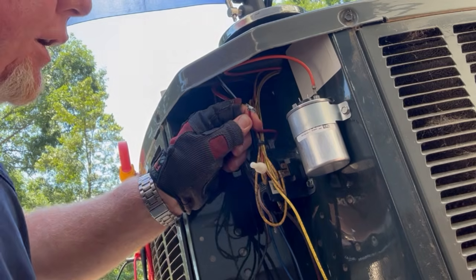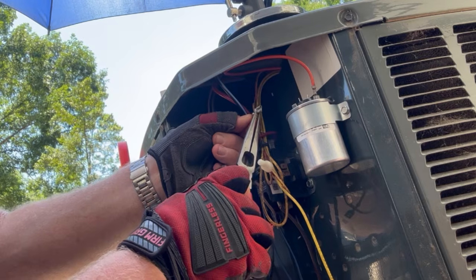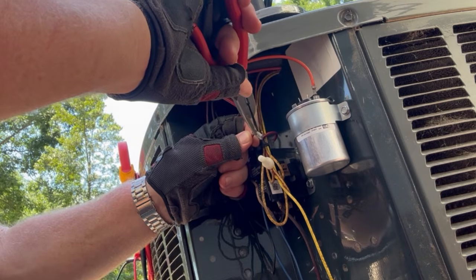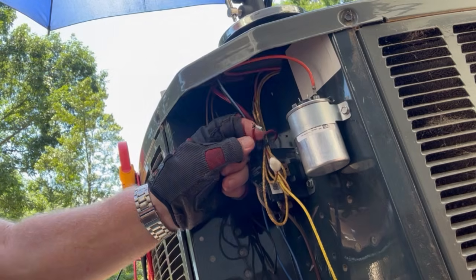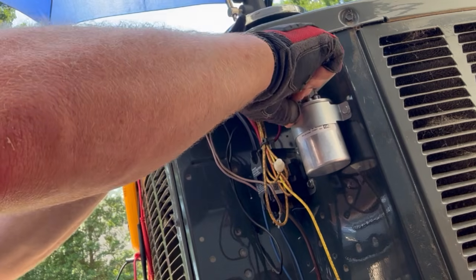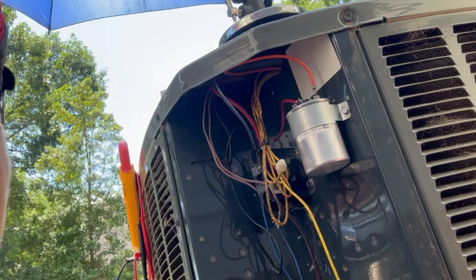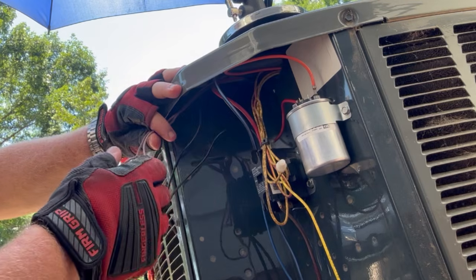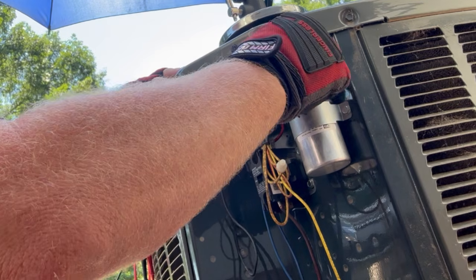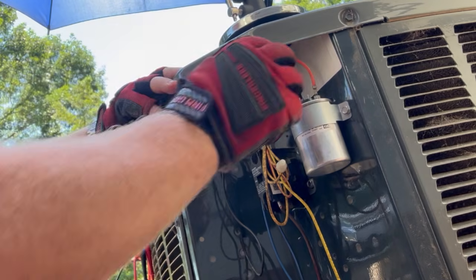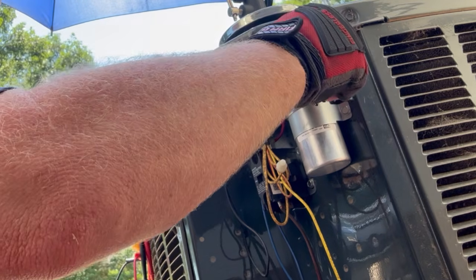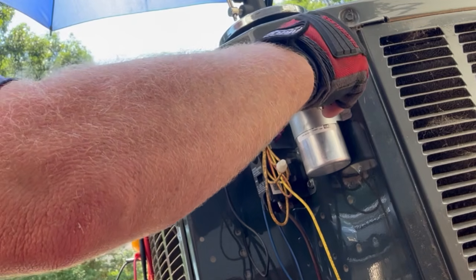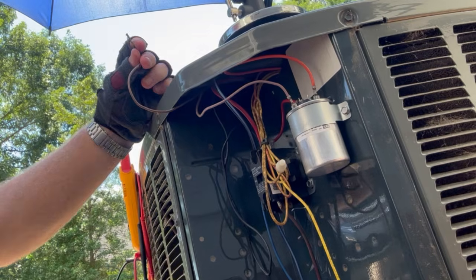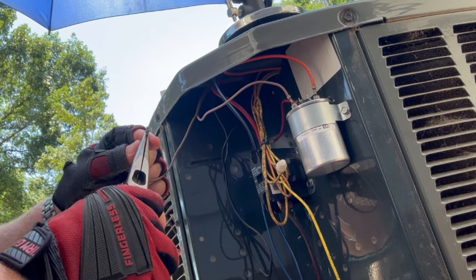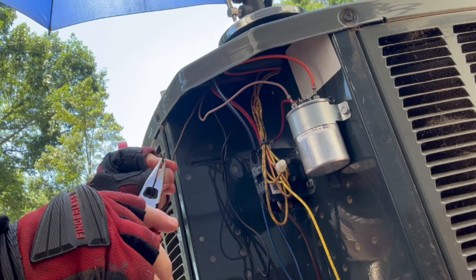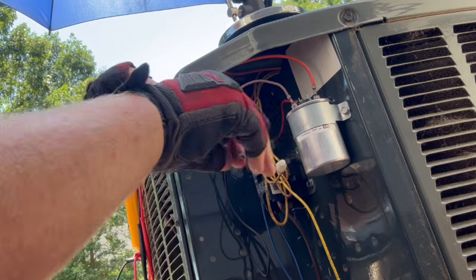And these little jumpers between the contactor and the common on the capacitor, always make sure they're on there snug, because if they're loose, that will be the wire that melts and burns, breaks. You end up with a recall. And it always comes at a bad time. It's always a bad time for the homeowner if it's something you could have prevented, but it always comes when we're busy, and then it gets squeezed on the schedule, and then you're working late and that kind of thing. So it is what it is. Make sure that one's on there tight.